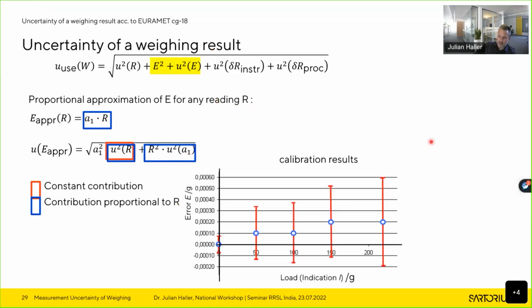So what is done basically is, if you have the calibration results at, in this case, 5 test loads, you will have the error of indication with a respective uncertainty of the error of indication. This is the calibration result. What is done then, for determining the uncertainty of any weighing result, is to approximate and interpolate that. You have a respective interpolation, that is this one, and also, of course, interpolation for the uncertainties, that is actually this formula.